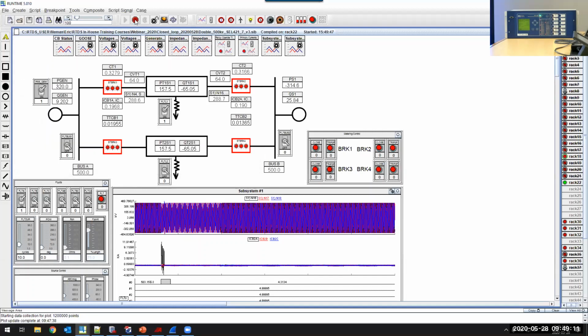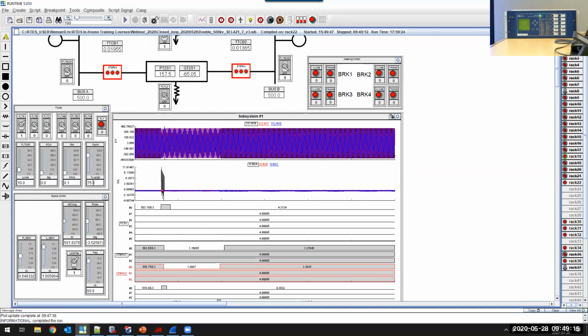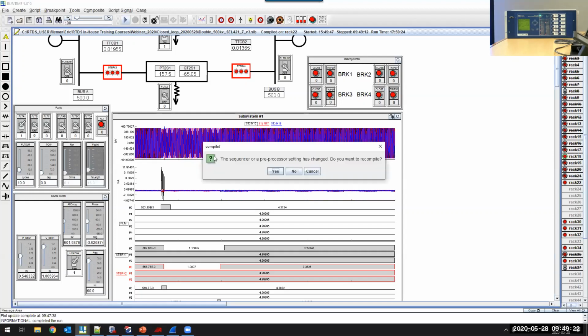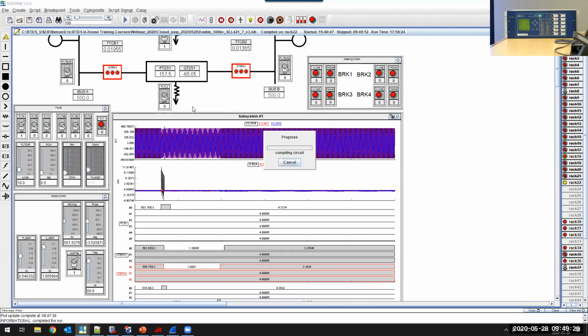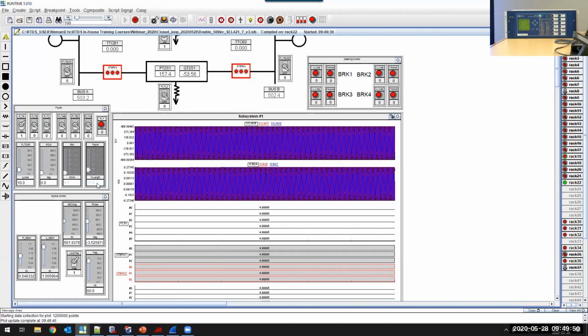So let's try one more scenario. Let's move the fault a little bit further away from the relay, so 15%. Whenever we need to change the draft variables, we need to stop the simulation. The draft needs to be recompiled, so you can just click the option there, and it will automatically recompile the case and then immediately rerun the case. When we set to 15%, it means the fault location is at 85% from the relay side, right? Remember that we set zone 1 of the relay to be 80%, so this is outside of zone 1, so it's a zone 2.